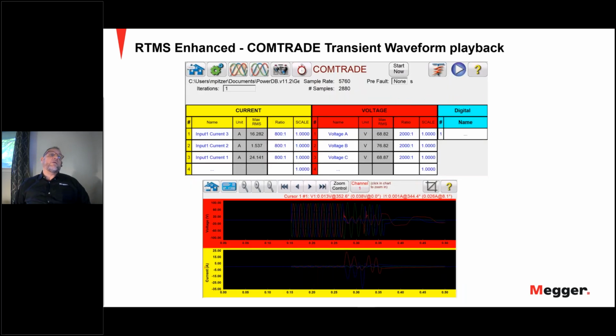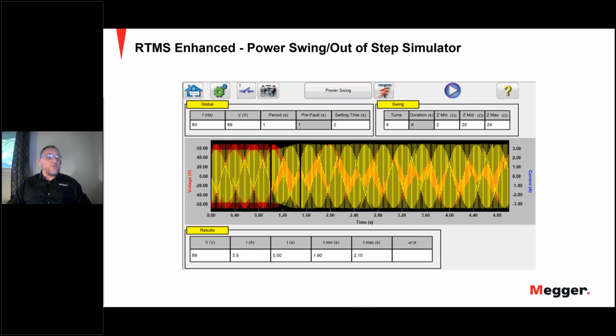Moving on to COMTRADE, the COMTRADE test option provides the capability of playing back transient waveform data from the SMRT relay test system. In other words, it can recreate a fault recorded by a digital fault recorder, protective relays, or a simulated fault using software tools like EMTP and ATP programs. Then power swing. The power swing simulation tool is similar to the power swing tool in the fault calculator, and it uses two superimposing waveforms of similar frequencies to provide a smooth impedance ramp.